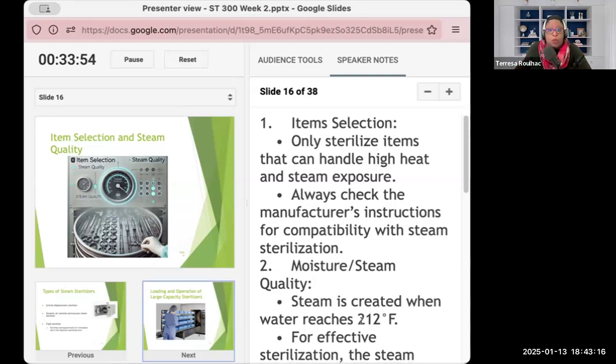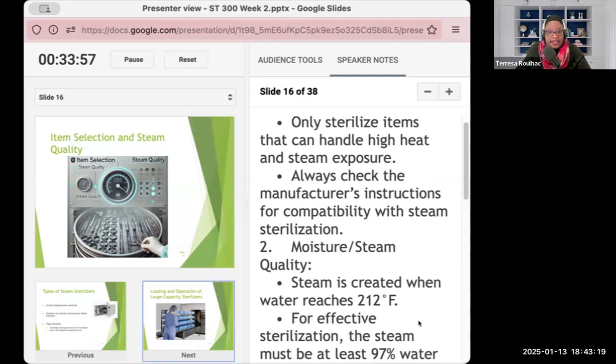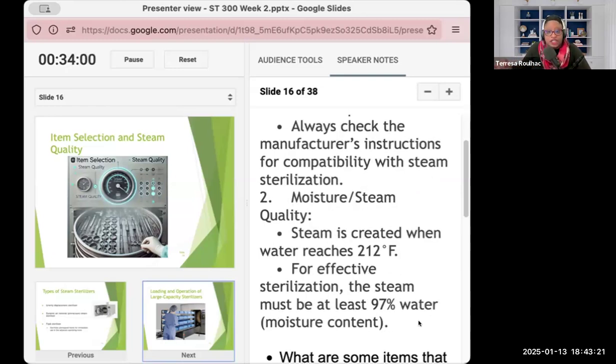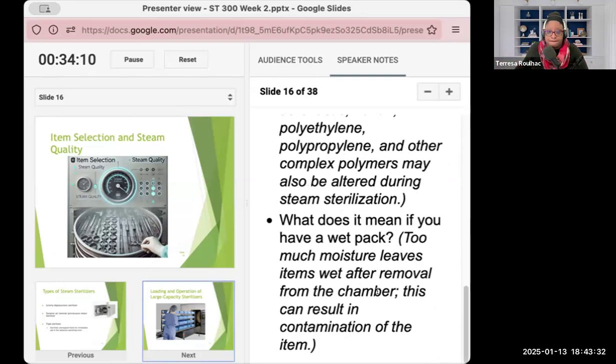Steam is created when water reaches 212 degrees Fahrenheit. For effective sterilization, the steam must be at least 97% water, which is just the moisture content. So you heard me say a wet load, okay? That's just too much moisture, or the chapter says wet pack. I'm using the terms we use in the operating room, the wet pack, wet load. So this is too much moisture, which leaves items wet after removal from the chamber. This can result in contamination of the item.